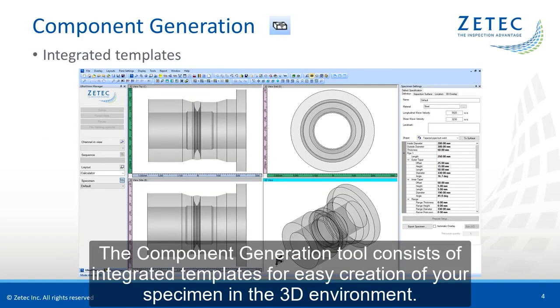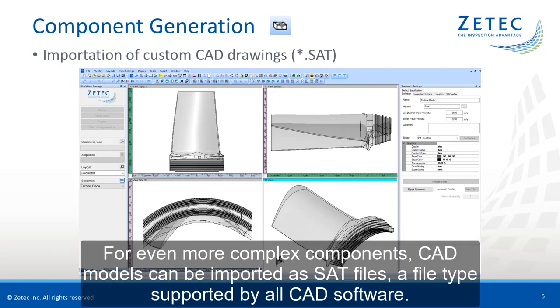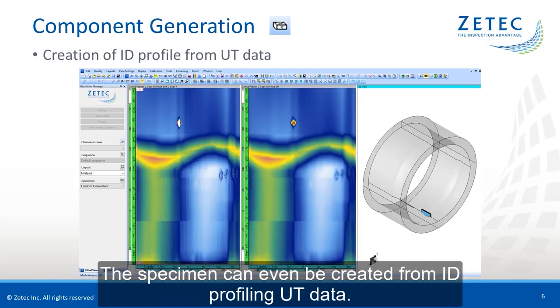The component generation tool consists of integrated templates for easy creation of your specimen in the 3D environment. For even more complex components, CAD models can be imported as SAT files, a file type supported by most CAD software. The specimen can even be created from ID profiling of UT data.